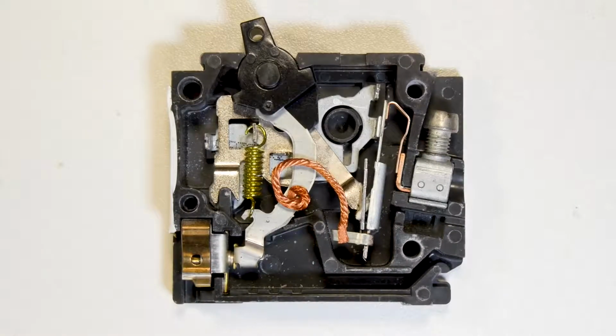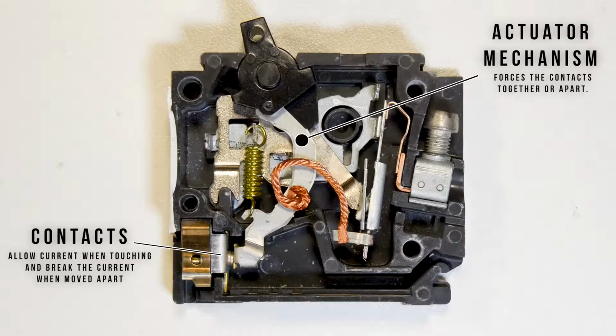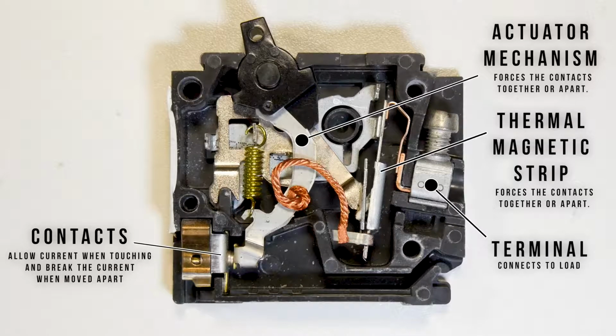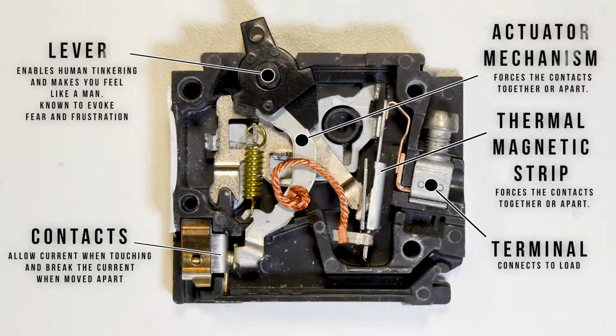Inside the circuit breaker, we find a couple of key components: the actuator mechanism, contacts, the terminals where we make the wire connections, the thermomagnetic strip, and last but not least, the lever that we use to turn a circuit breaker on or off, or reset it in case it trips.